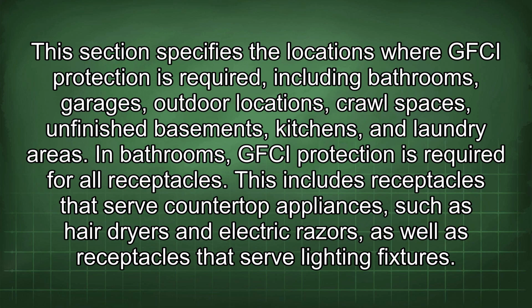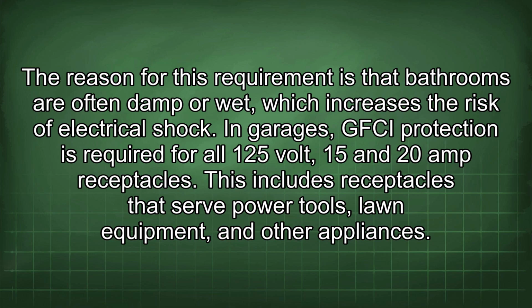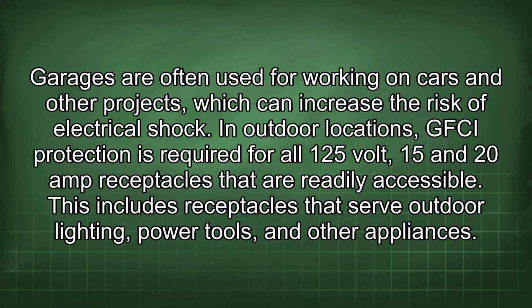This includes receptacles that serve countertop appliances such as hairdryers and electric razors, as well as receptacles that serve lighting fixtures. The reason for this requirement is that bathrooms are often damp or wet, which increases the risk of electrical shock. In garages, GFCI protection is required for all 125-volt, 15 and 20 amp receptacles. This includes receptacles that serve power tools, lawn equipment, and other appliances. Garages are often used for working on cars and other projects, which can increase the risk of electrical shock.